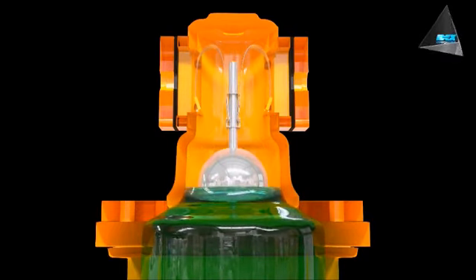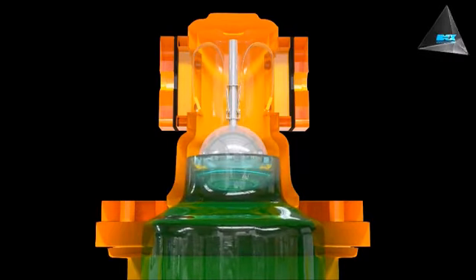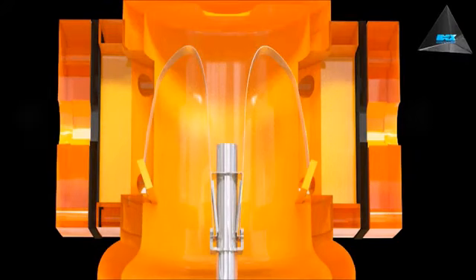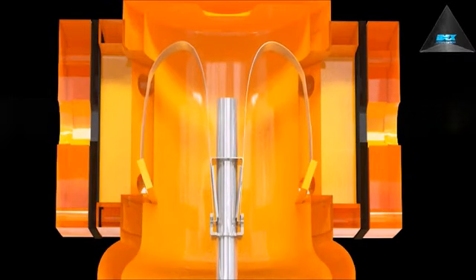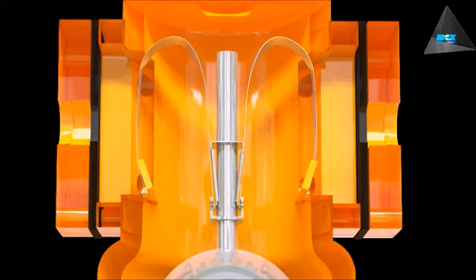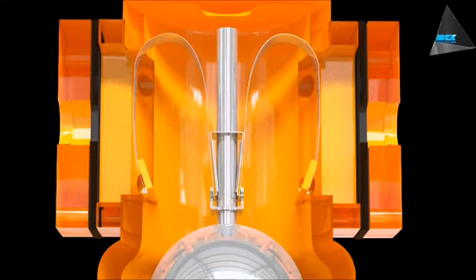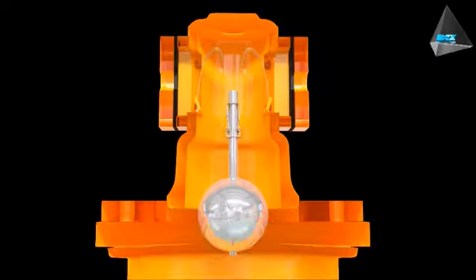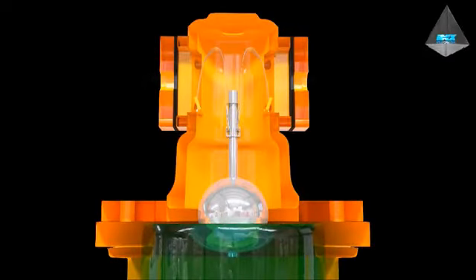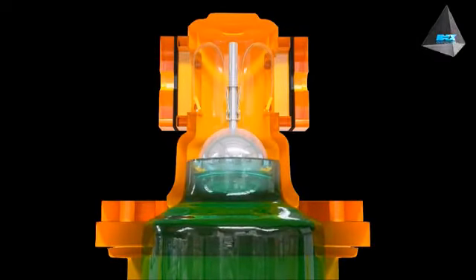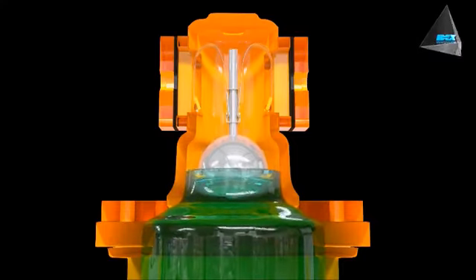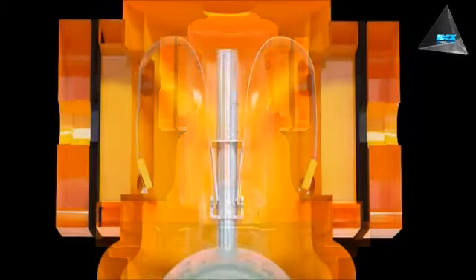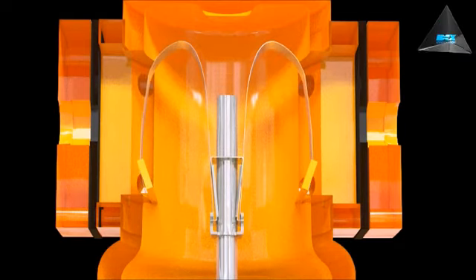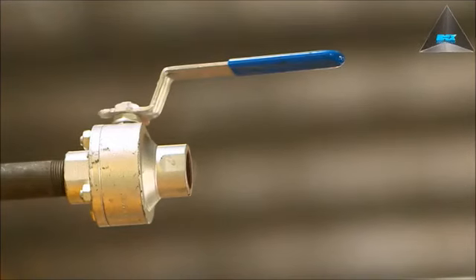As the product enters, it displaces the air, allowing the float to rise. As the float rises, the 2 reeds cover the vent ports. This stops the venting of air and prevents any product from leaking out through the vent ports. If free air enters the system, it will rise and displace the liquid. As the liquid level drops, so will the float. As the float drops, the 2 reeds are drawn away from the center vent port and free air vents from the system. This cycle is repeated anytime free air enters the metering system.